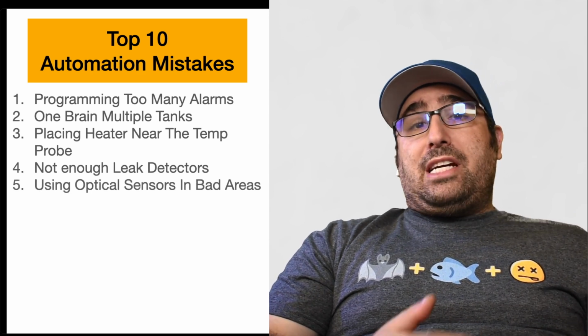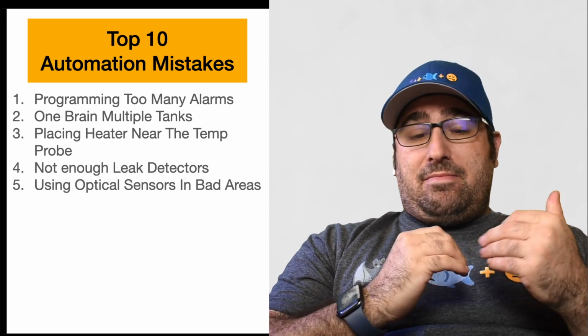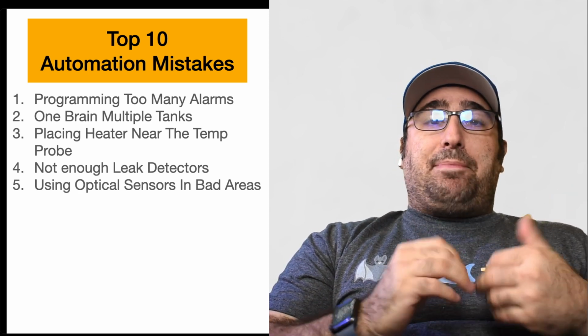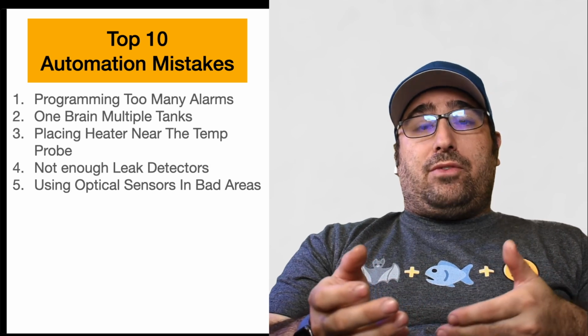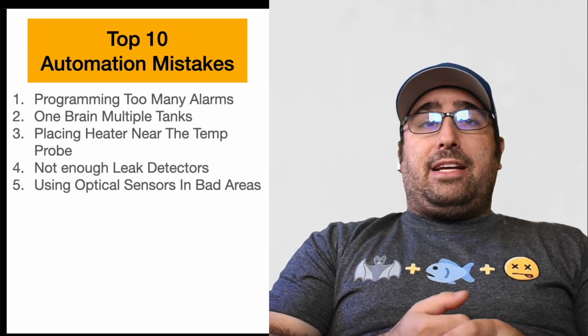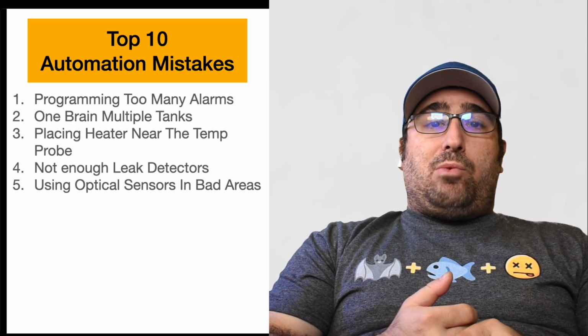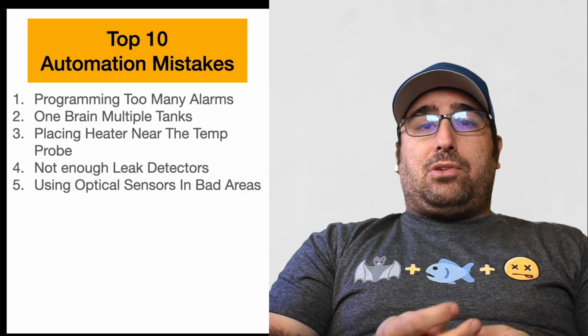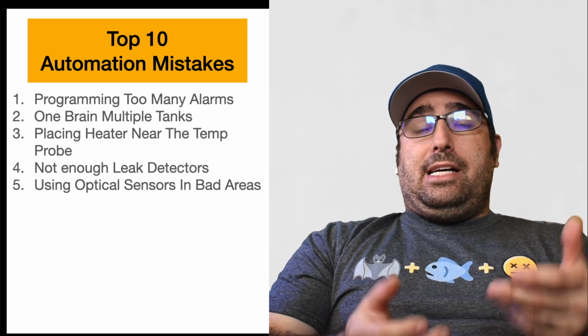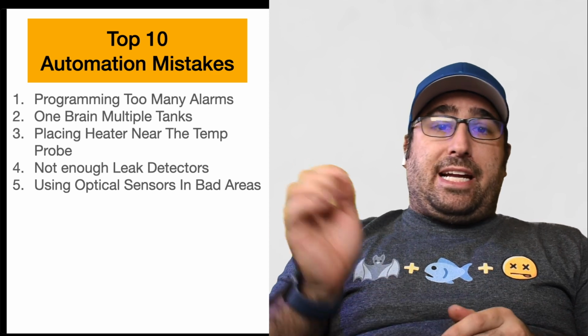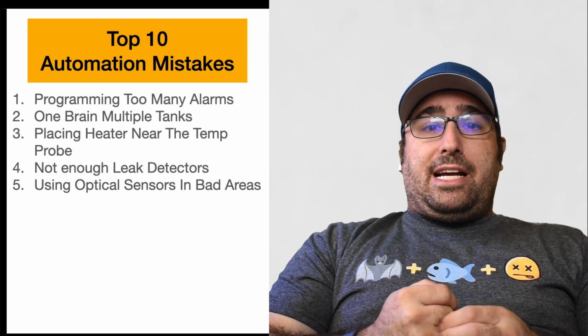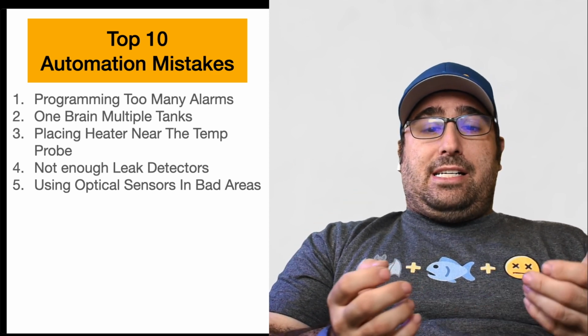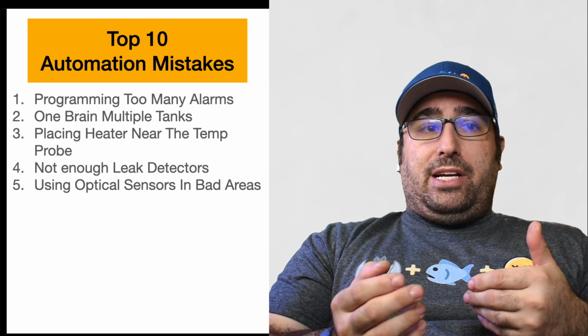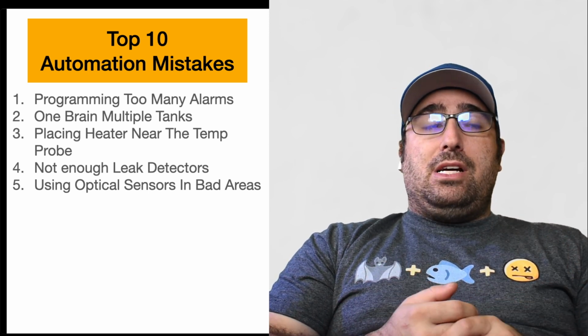Number five is using optical sensors in bad areas, and I am notorious for doing this. Optical sensors, when they get dirty or get full of salt or any type of grime, tend to just stop working. So my recommendation here is to always put your optical sensors in a very clean area. For instance, don't put them inside a kalk stirrer. Don't put them inside a dosing container that is going to be doing any type of mixing whatsoever.